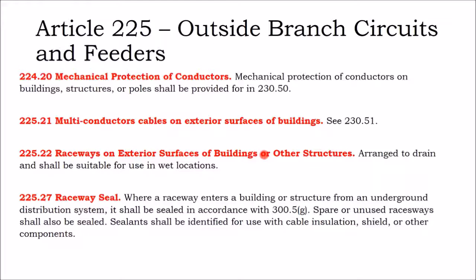Well, you don't want to arrange your wires and conduit such that, let's say you put the box at the bottom of the rooftop instead of the top of the roof. If your entry point is at the bottom of the rooftop, it could be that the water is flowing down the roof and then it might run into the box. And I've seen this before on a rooftop. We put a pipe boot on a large piece of conduit and ran it into a PVC box. And there are a few things that did not get done on that box. And what happened in this case was, it was the combination of a heavy rain is when they noticed the water coming into the rooftop.